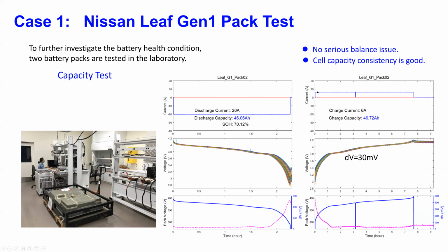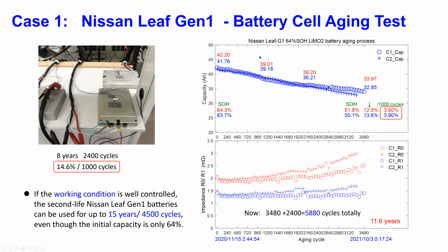So looking at the pack testing, you can see some of the data displayed here. We performed discharge and charge, and looked at the capacity. For example, this pack has 70% of capacity left. We also looked at the cell voltage of each cell inside the pack, and the impedance, and so on. We found that this cell capacity is pretty consistent, and there are no serious balance issues with the battery packs.